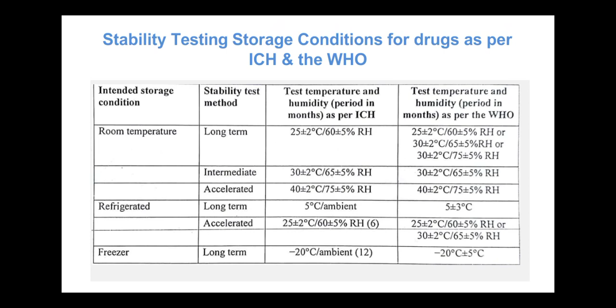For refrigerated medicines, long term means 5 plus or minus 3 degrees centigrade test temperature. Accelerated stability testing is 25 plus or minus 2 or 60 plus or minus 5 RH. For the freezer, long term is minus 20 degrees centigrade that we have to maintain as the test temperature.